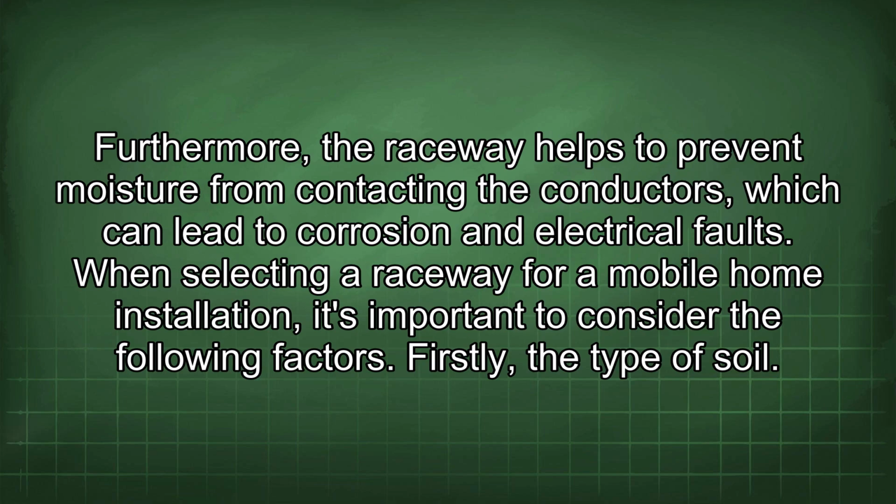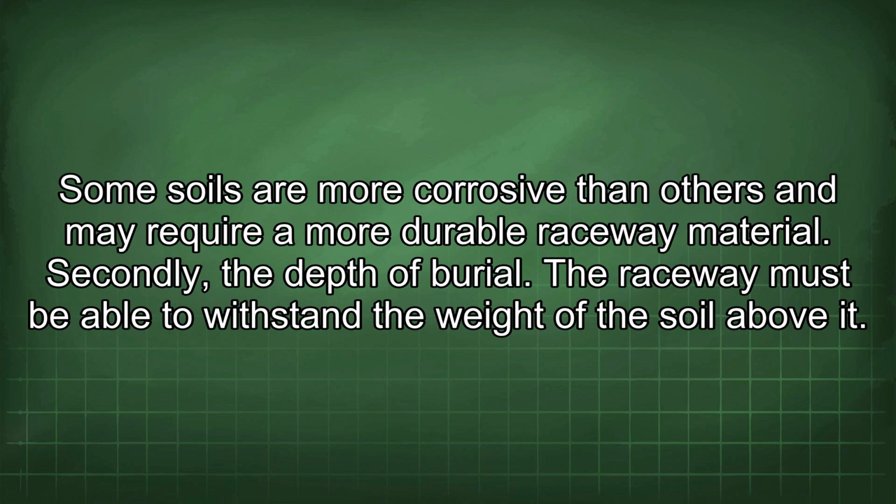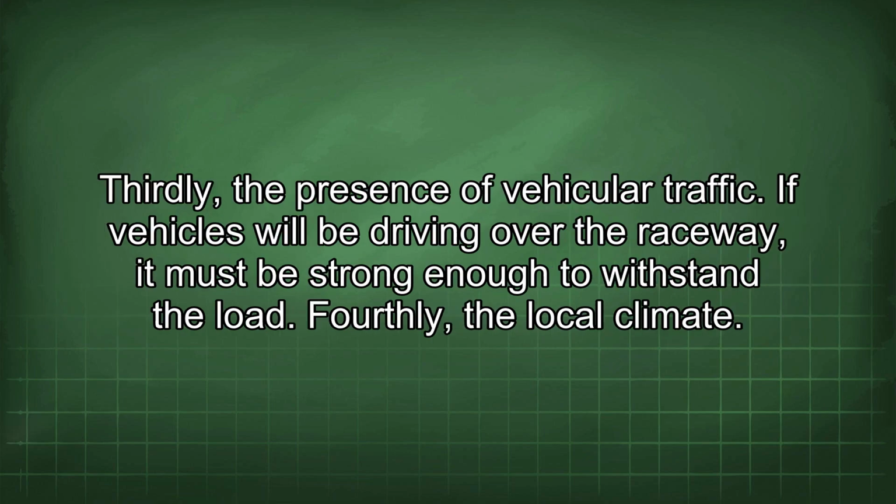Firstly, the type of soil. Some soils are more corrosive than others and may require a more durable raceway material. Secondly, the depth of burial. The raceway must be able to withstand the weight of the soil above it. Thirdly, the presence of vehicular traffic. If vehicles will be driving over the raceway, it must be strong enough to withstand the load.